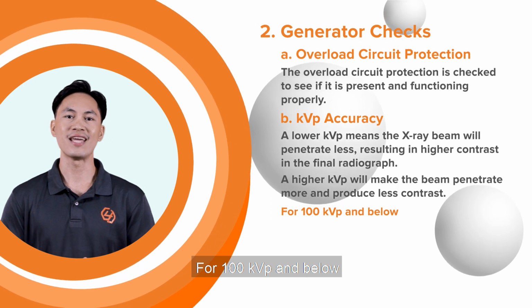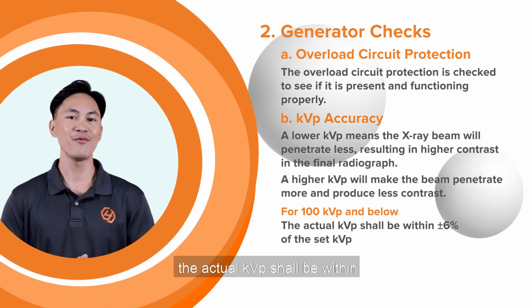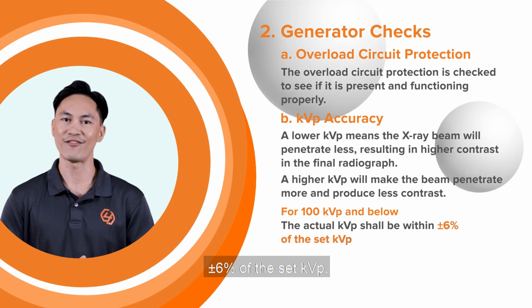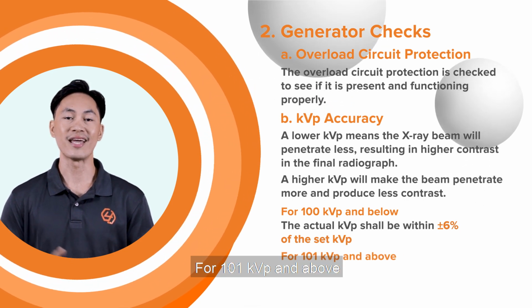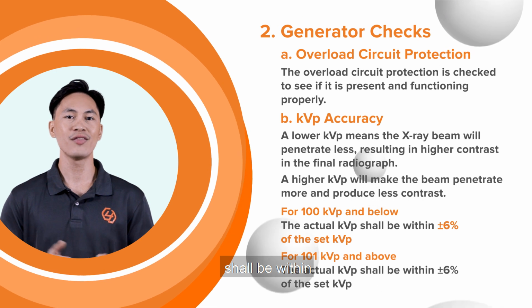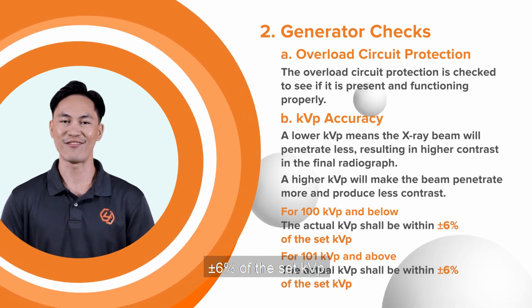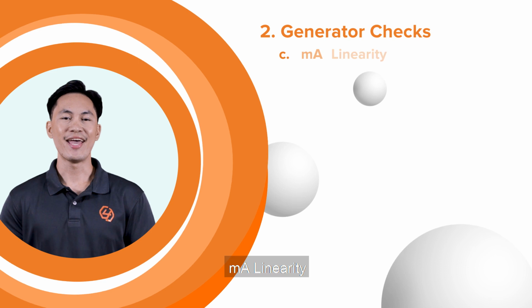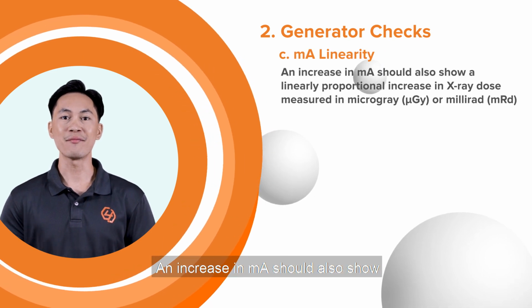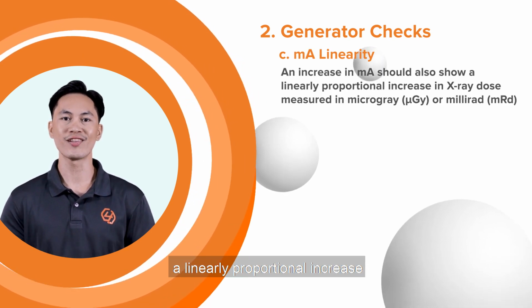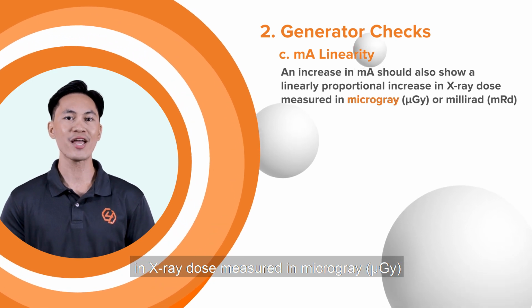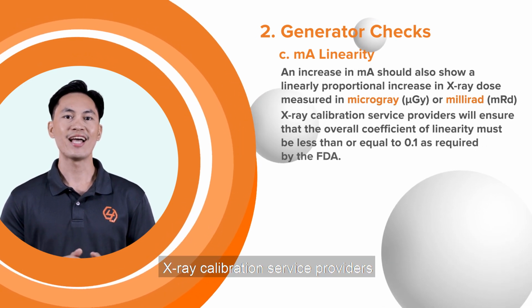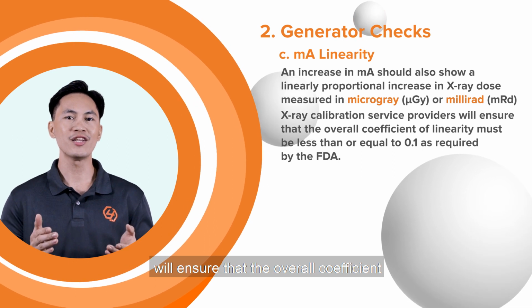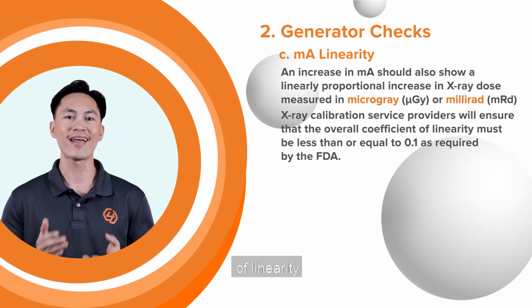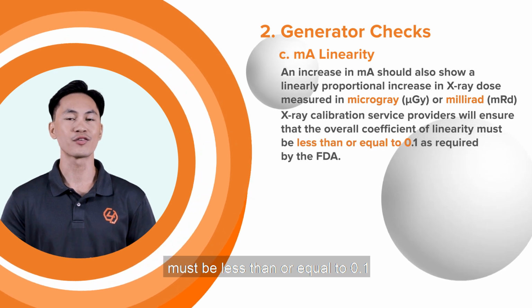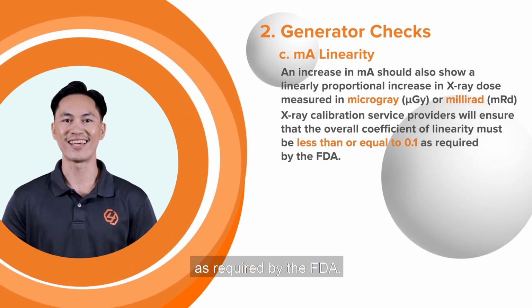For 100 kVp and below, the actual kVp shall be within ±6% of the set kVp. For 101 kVp and above, the actual kVp shall be within ±6% of the set kVp. C. mA linearity. An increase in mA should also show a linearly proportional increase in X-ray dose measured in microgray or millirad. X-ray calibration service providers will ensure that the overall coefficient of linearity must be less than or equal to 0.1 as required by the FDA.